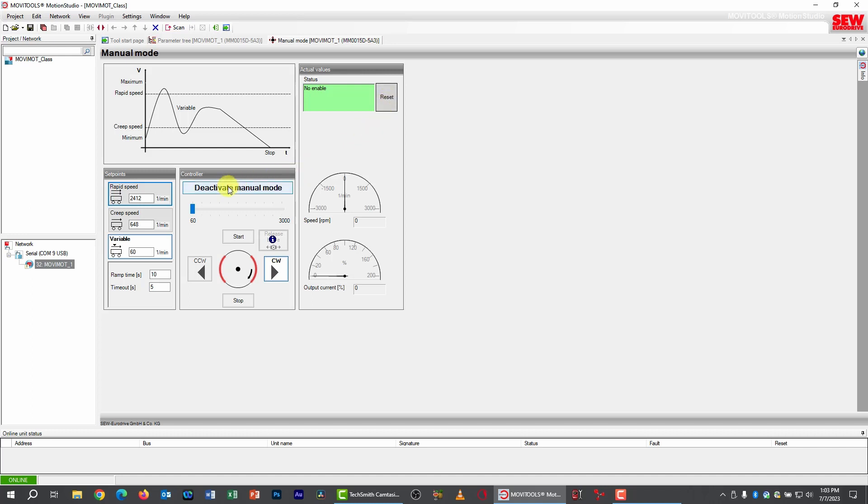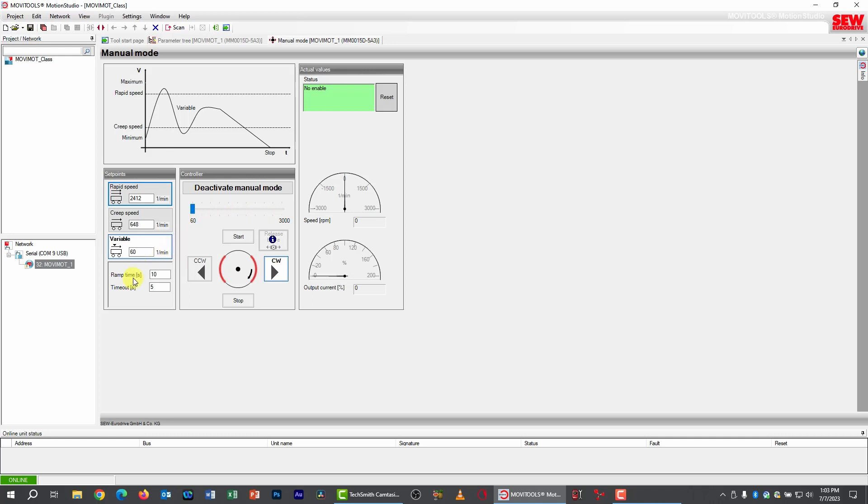You can reset faults here with the Reset button. And then over here, finally, we have a number of buttons that allow us to switch between fixed speeds, like a rapid one and a creep speed. We have a variable speed button here that reactivates the slider so you can control the speed that way. And then we have a ramp value down here. I notice that ramp value is pretty long, it's 10 seconds. Let me change this to something a little shorter, we'll change it to 2 seconds.